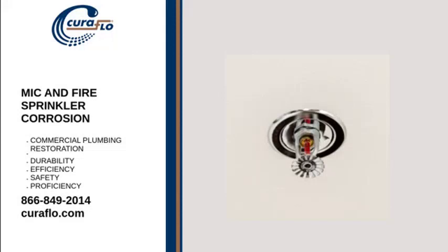To prevent MIC in fire protection systems, it is crucial to be proactive by testing the water supply regularly and determining the bacteria types present so that adequate treatment can be applied.